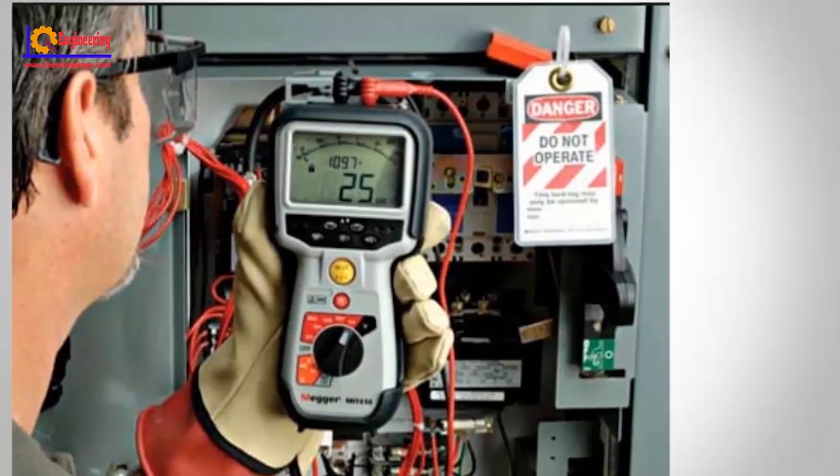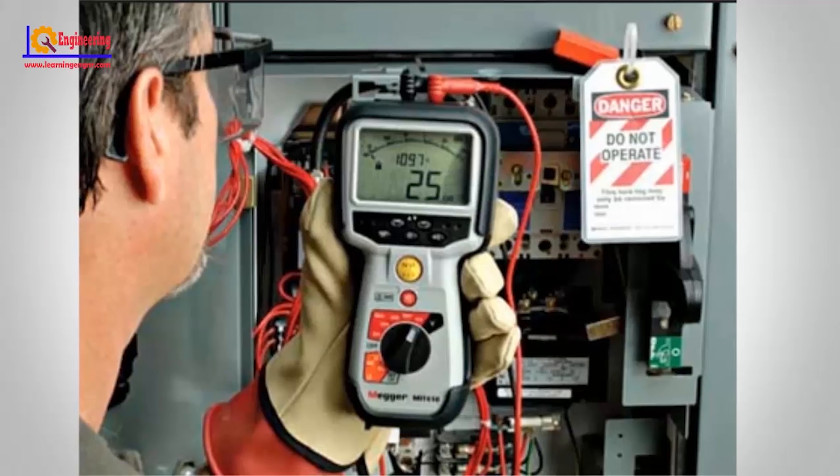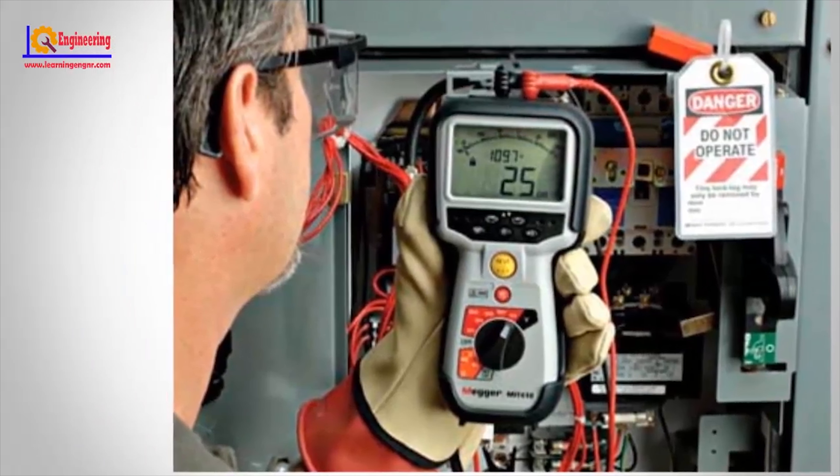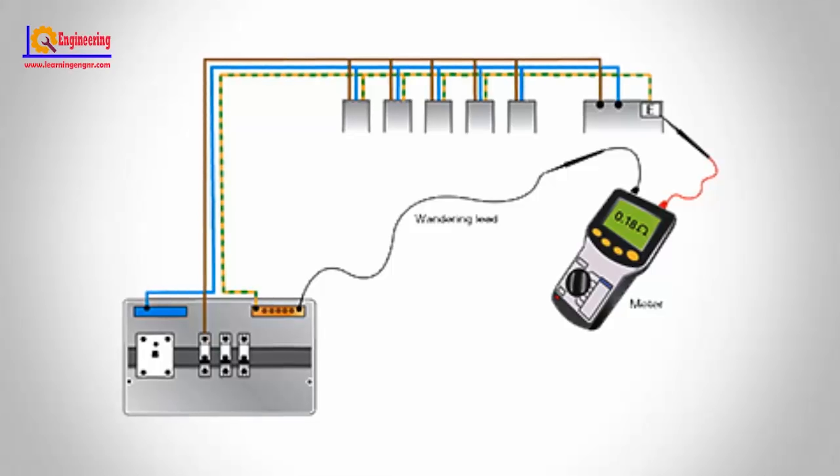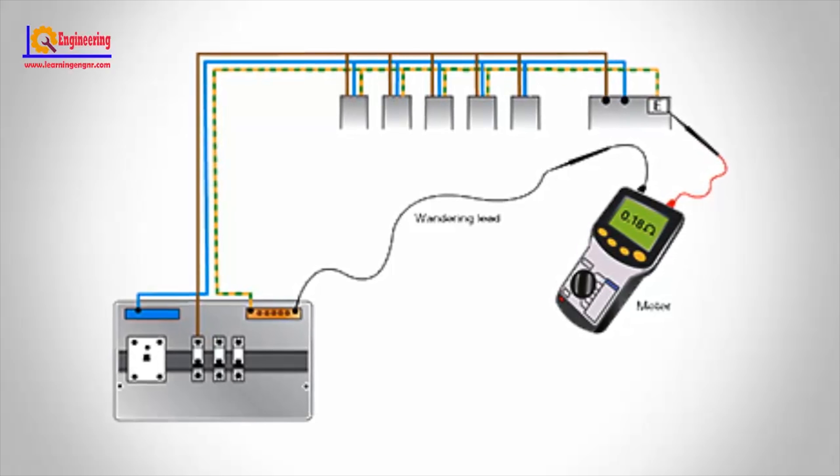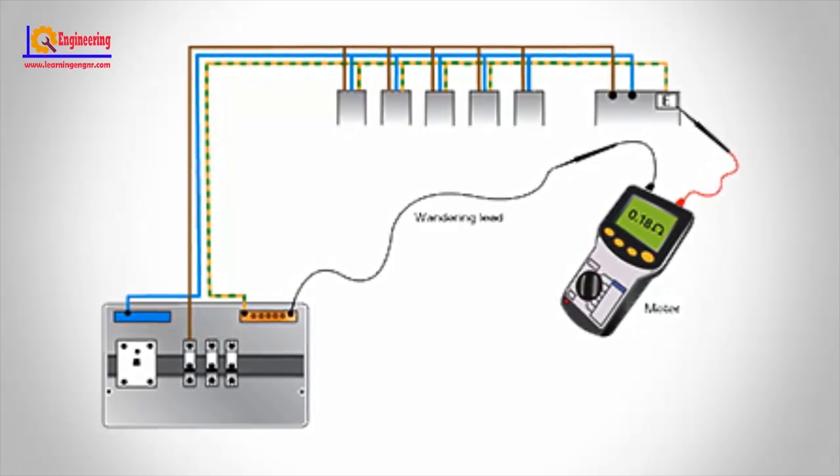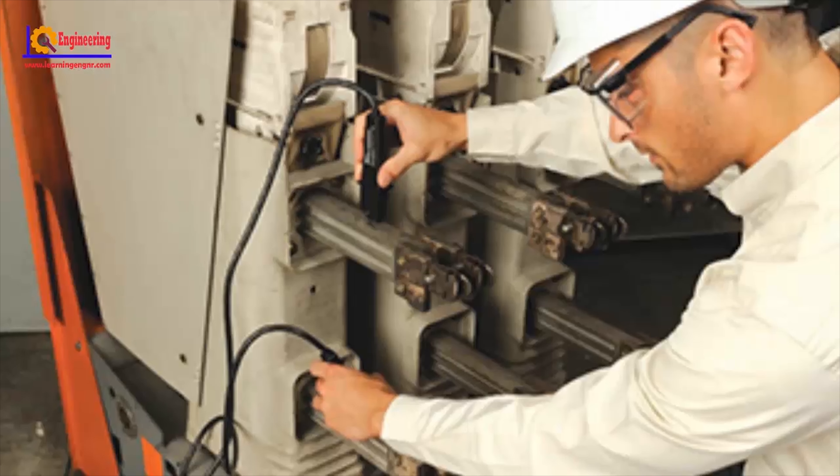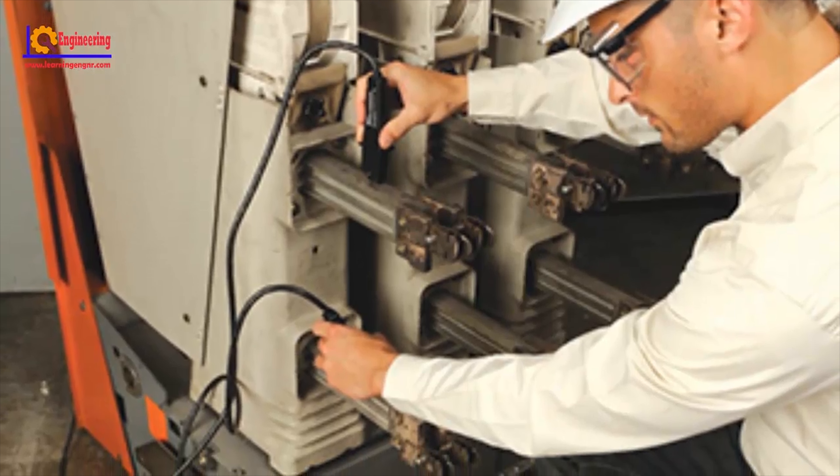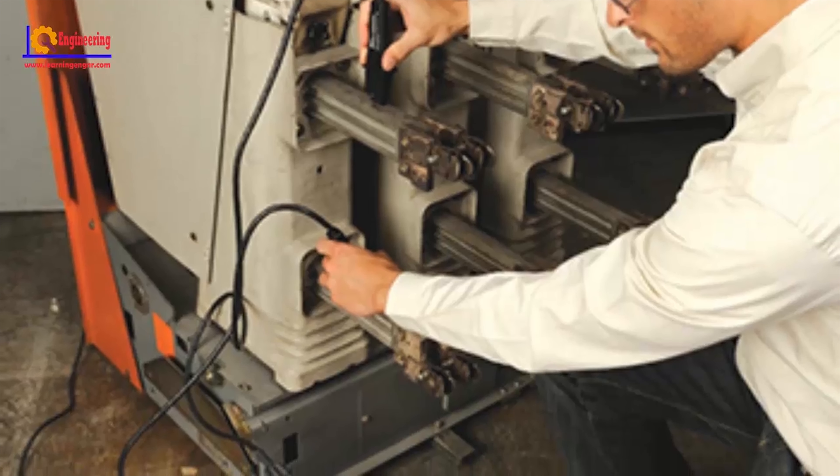Earth Continuity Test. This test is performed by measuring the resistance between the third pin ground and outside metal body of the product under test.